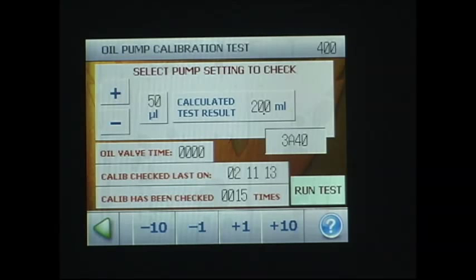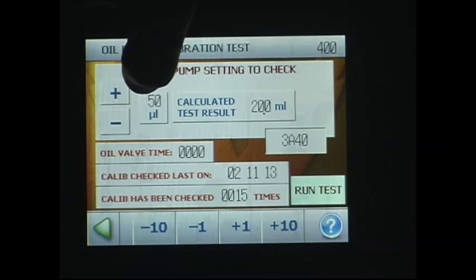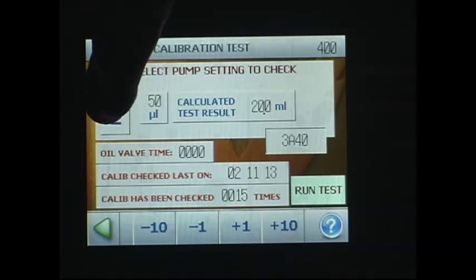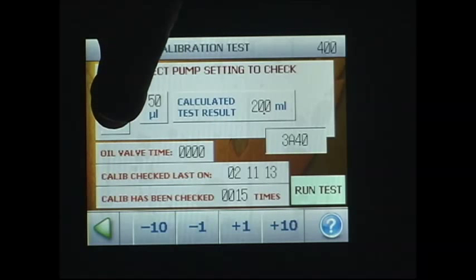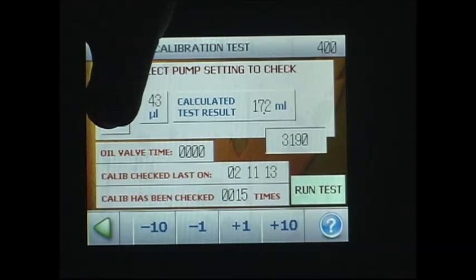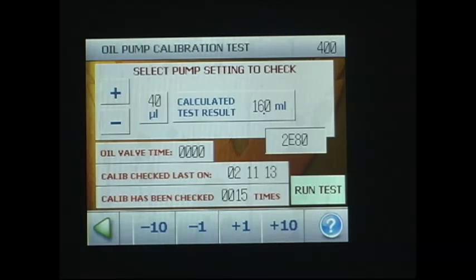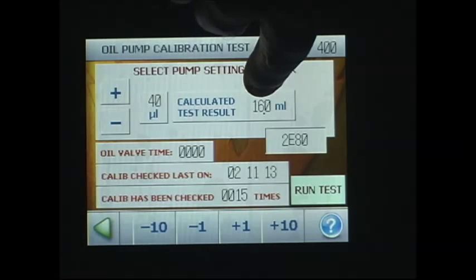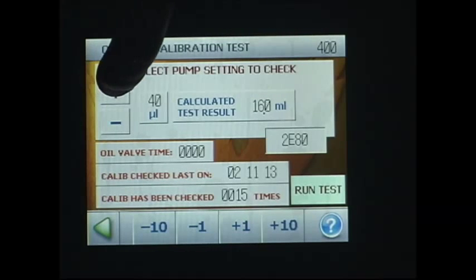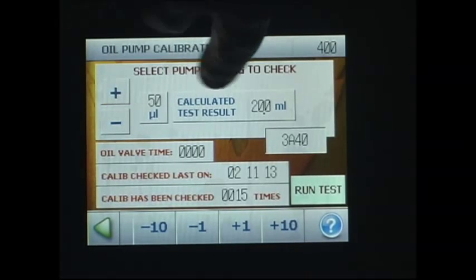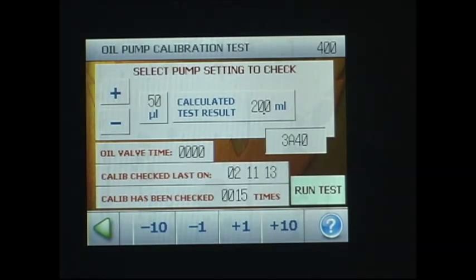As you can see on the screen, this is selecting our microliters per board. Most of the newer patterns are set for 50. Some of the older ones are at 40. But you have anywhere from 30 to 60. So if I wanted to go down to a 40 mic, it tells me when I run my test I should have 16 mils in the graduated cylinder. If I want a 50 mic, I should have 20 in my graduated cylinder.